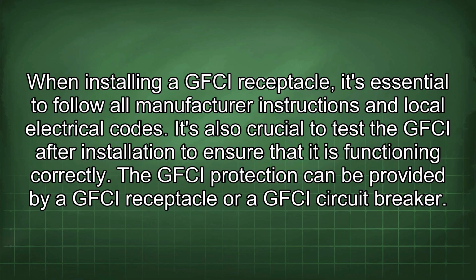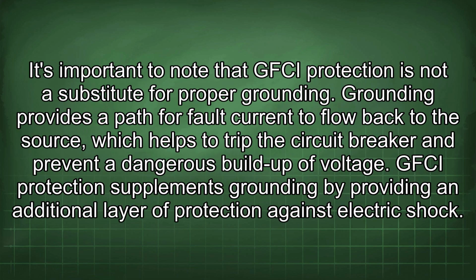When installing a GFCI receptacle, it's essential to follow all manufacturer instructions and local electrical codes. It's also crucial to test the GFCI after installation to ensure that it is functioning correctly. GFCI protection can be provided by a GFCI receptacle or a GFCI circuit breaker. It's important to note that GFCI protection is not a substitute for proper grounding. Grounding provides a path for fault current to flow back to the source, which helps to trip the circuit breaker and prevent a dangerous buildup of voltage. GFCI protection supplements grounding by providing an additional layer of protection against electric shock.